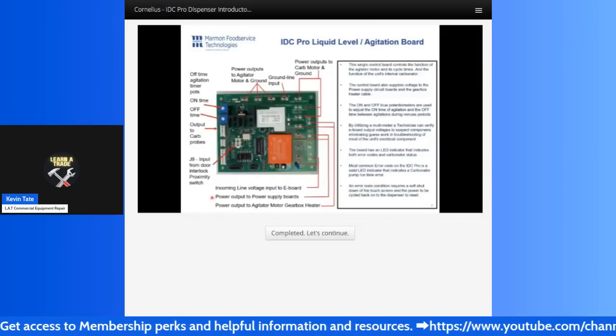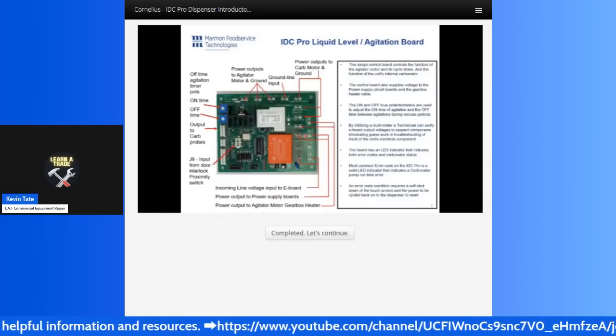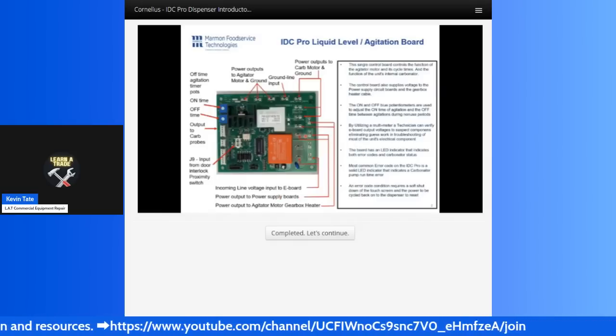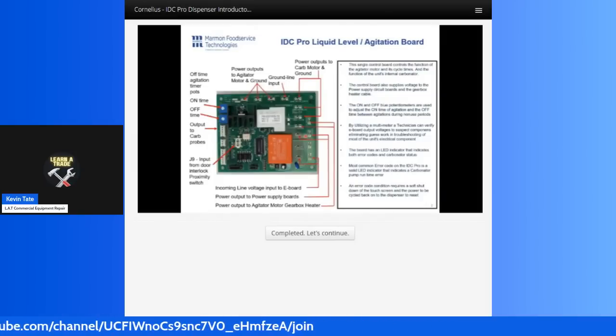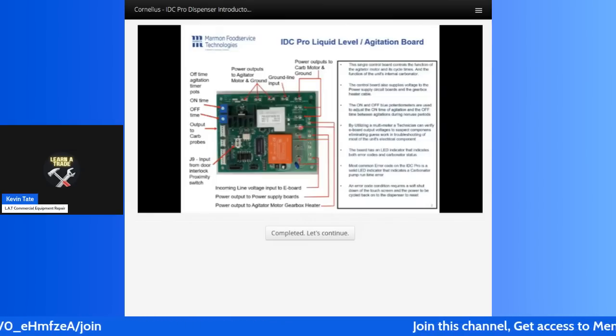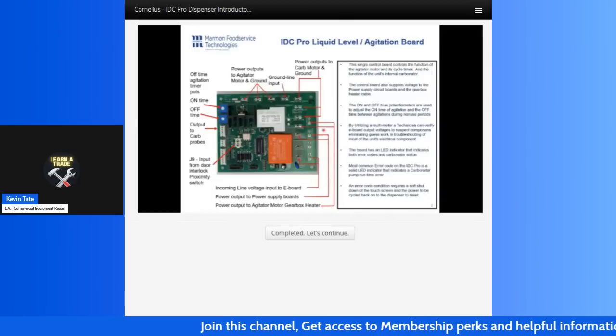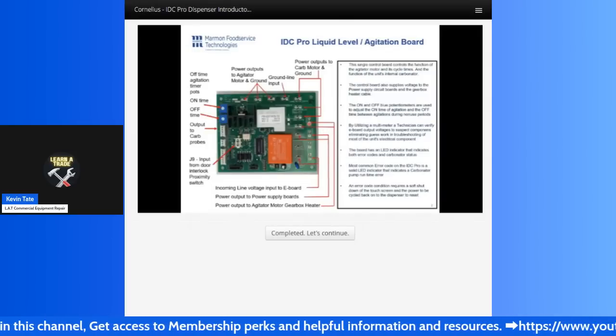The next one, the power output to those power supply boards. That's these two terminals here, and that supplies those power supply boards, which in turn supply a lower reduced voltage to the solenoids and some other components in the unit. And we'll talk about that in another video. Power output to the agitator motor heater gearbox. The gear motor has a heater cord wrapped around it that is on all the time, and there's a reason for that, and we'll talk about that in another video.